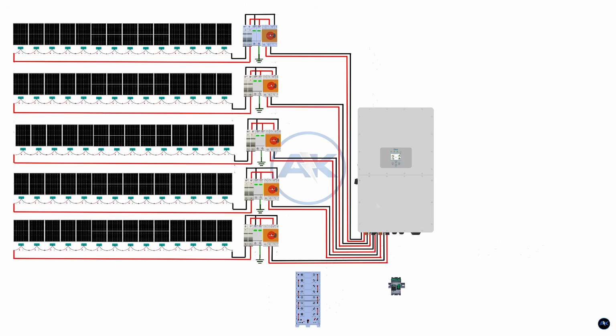Before starting, make sure the inverter is completely powered off, the DC isolator is off, and all battery breakers are in the off position. High-voltage batteries are always installed in series inside the battery rack by the manufacturer. You should never change the internal battery configuration. Your job is only to connect the battery output terminals to the inverter.